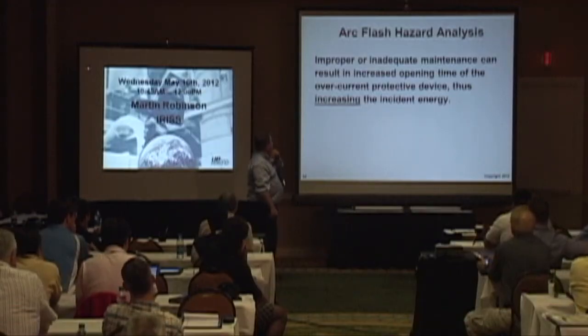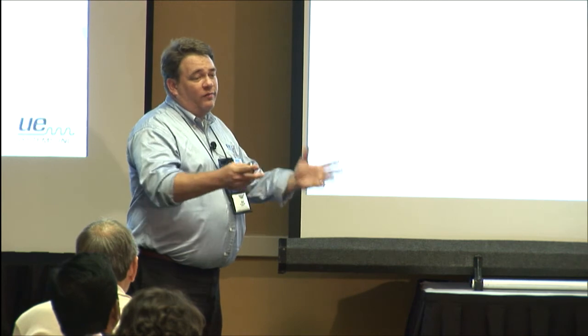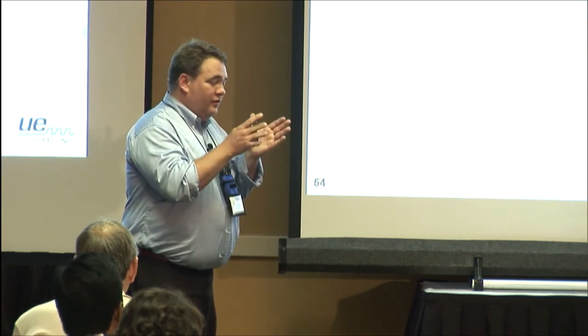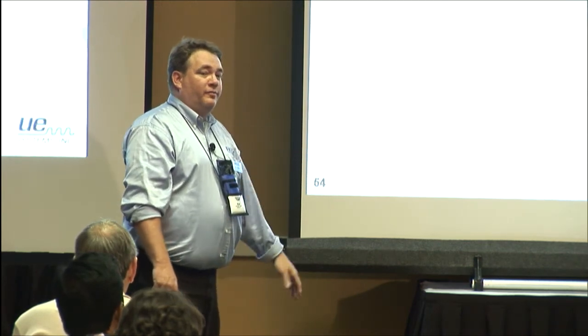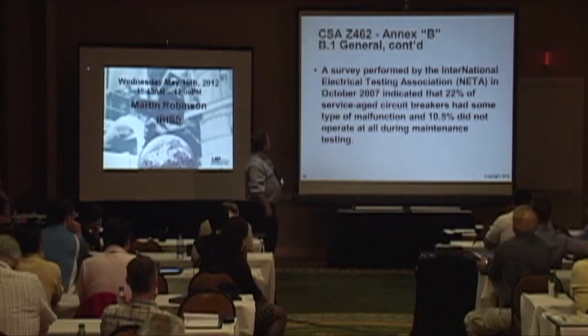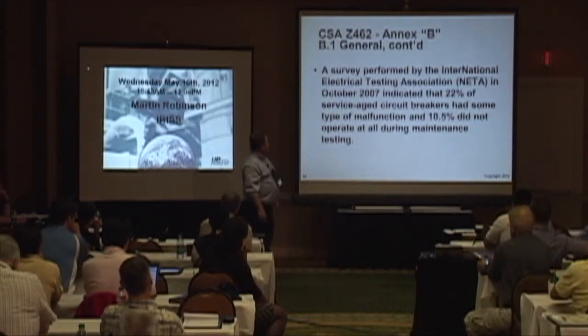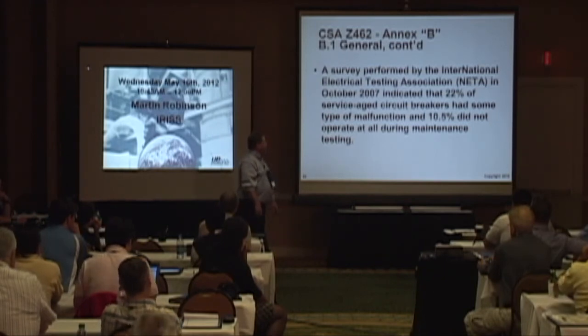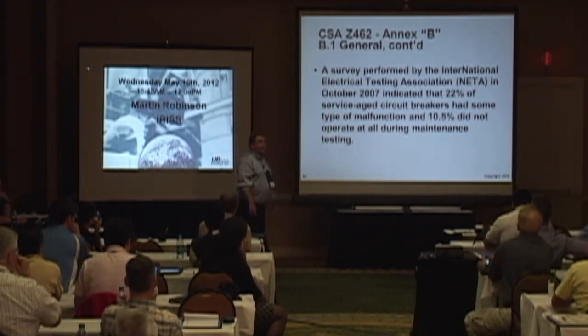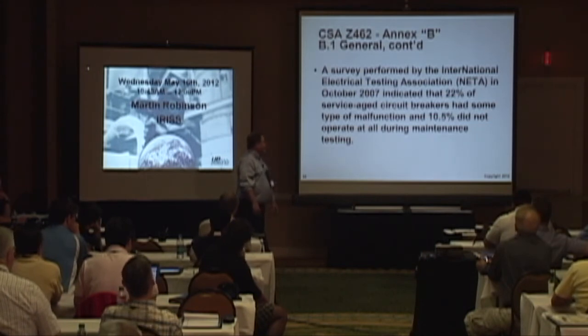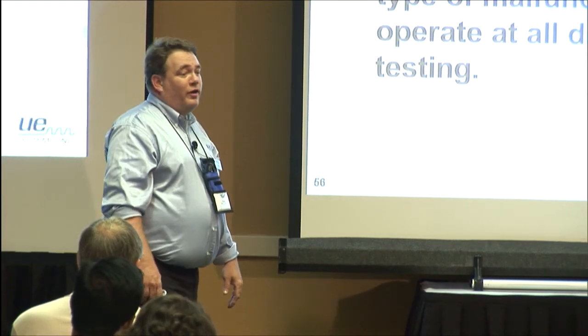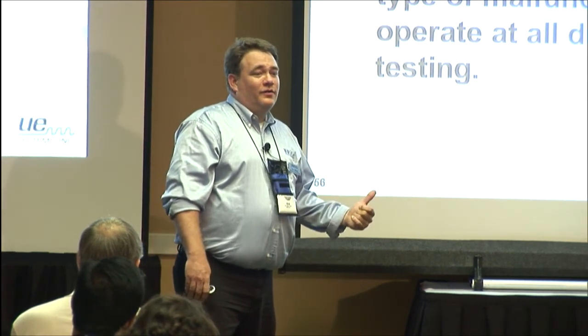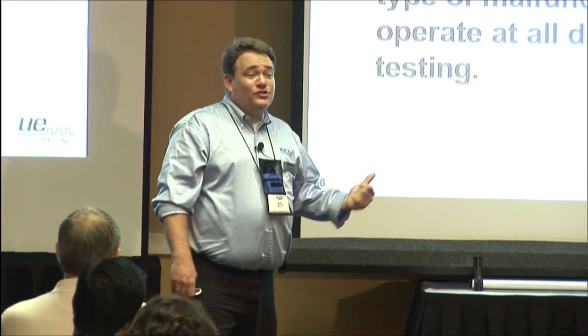Arc flash hazard analysis: improper or inadequate maintenance can result in increased opening times of the overcurrent device, increasing the incident energy. If you go through and you do all the math, the time it takes for the overload device to trip is a direct multiplier. So looking at a survey by NETA in 2007, it indicated that 22% of the service-age breakers had some type of malfunction, and 10.5% of them did not operate at all. So because that breaker stays closed all the time and doesn't get exercised and doesn't get checked out, when it actually comes time for an overcurrent condition, it doesn't trip.